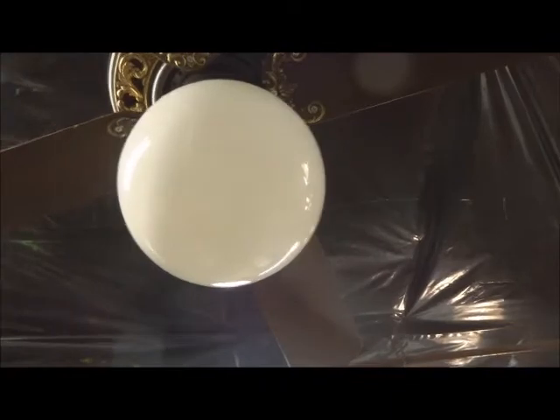Turn off the high switch so I can stop it by hand, and we are going to do what's called zero to high — just turn it on straight high and watch the meter. No inrush. I never saw an inrush current go above what it draws, so turn it off. I guess that is all I have for this.